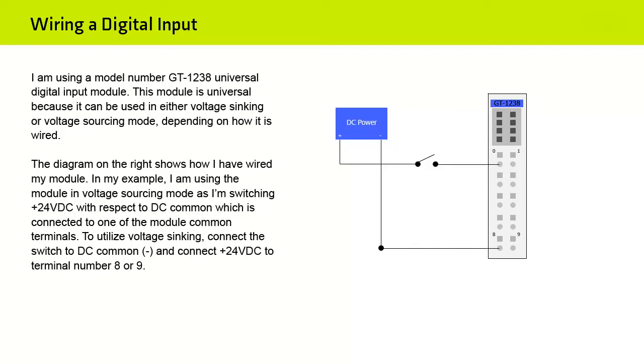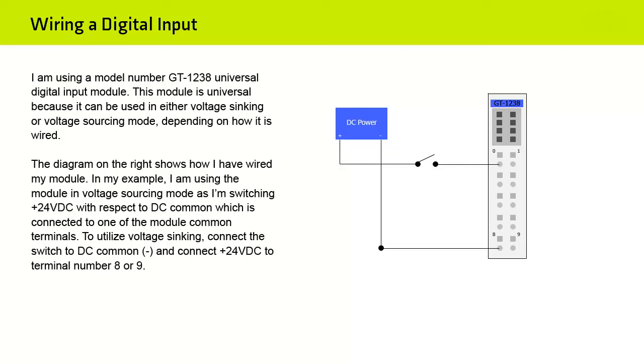I am using a model number GT-1238 universal digital input module. This module is universal because it can be used in either voltage sinking or voltage sourcing mode, depending on how it is wired. The diagram on the right shows how I have wired my module. In my example, I'm using the module in voltage sourcing mode as I'm switching plus 24 volts DC with respect to DC common, which is connected to one of the module common terminals. To utilize voltage sinking, connect the switch to DC common and connect plus 24 volts DC to terminal number 8 or terminal number 9.